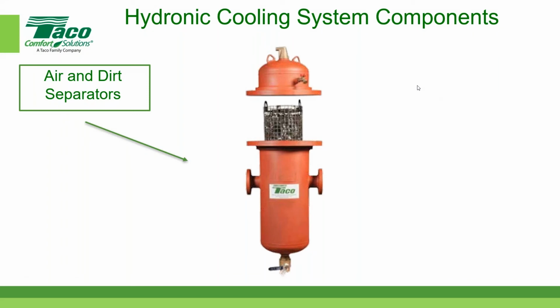Good stuff. We've got all kinds of fun stuff this evening. Someone just made a comment, and it's true. Many of these components that you talked about during last week or month's presentation on the hot water systems, yes, they're common to both the hot water and the chilled water. And as Brett pointed out, when it comes to certain components, you may want to have them insulated because they will sweat if they're not properly insulated, especially if you have a mechanical room in the summertime that's ventilated with outside air, not air conditioned, and the dew point temperature is probably close to 55 degrees or even higher in extreme weather, and the chilled water is circulating at around 42 to 54, which is well below the dew point temperature, so it will definitely sweat. And that's why insulation is so important for these different kinds of components.